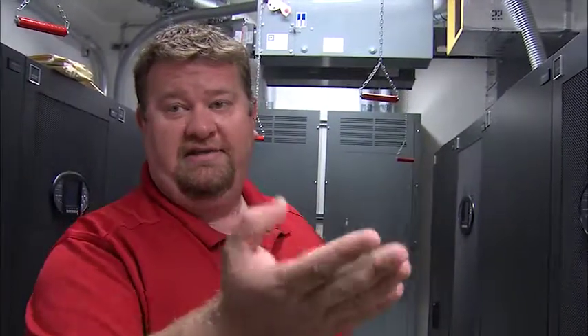The question was, if we lose utility power, how can we tell on these UPS systems? Number one, they'll beep. And like I said earlier, most of your power outages are 3 seconds. If they're longer than 3 seconds, your ATS kicks over to generator within 10 seconds, you said? So you only hear them beeping if you're walking by. Once we have the communications up and running, you'll get email alerts, notifications that you just went on to battery. And then once the generator comes on and it clears off the battery, it'll go back to normal, it'll say normal power.